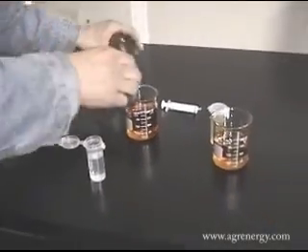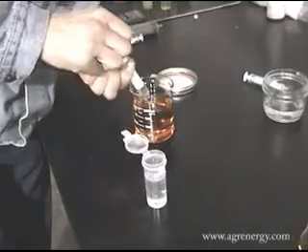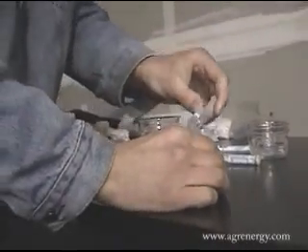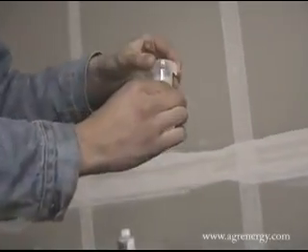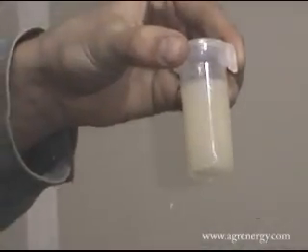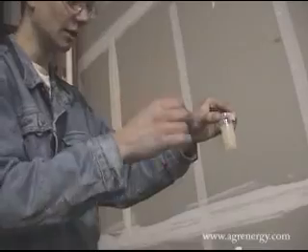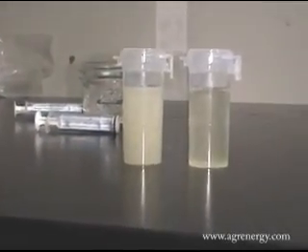Then we take our 3 milliliter sample of fuel and we put that in the sample of methanol. And just like last time, we seal the lid completely, close the safety snap, shake it up, and we see a tremendously foggy appearance. This is due to the fact that this sample has not dissolved well into the methanol. So this fogginess is caused by small globs of undissolved fuel floating around in here. We see a very marked difference between this and the sample that's likely to pass ASTM.